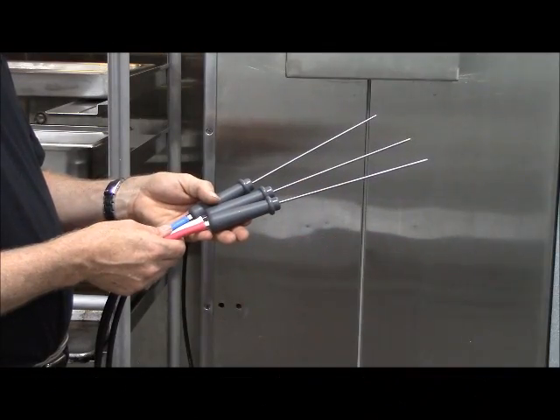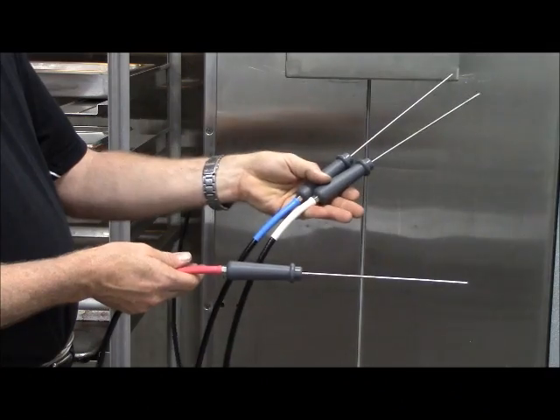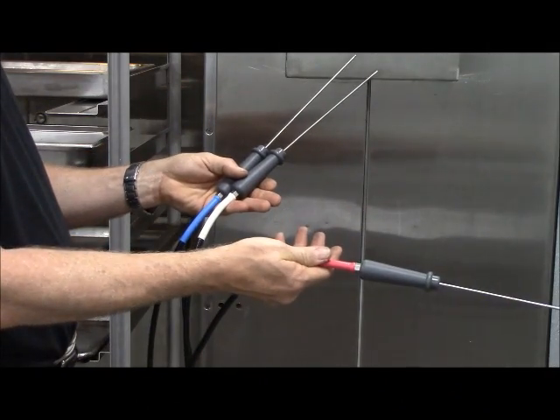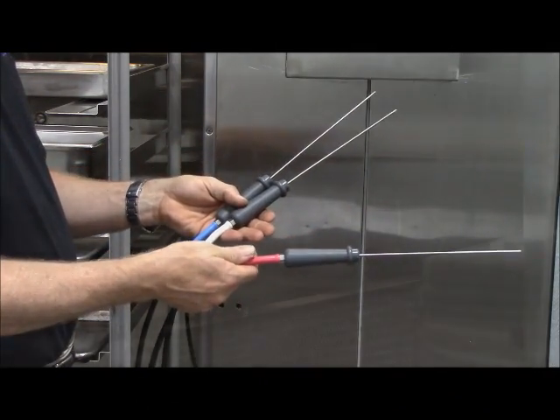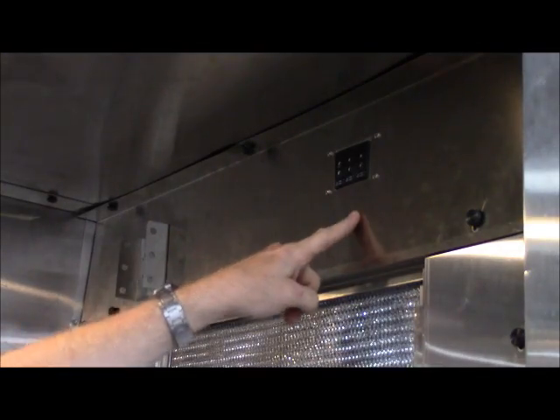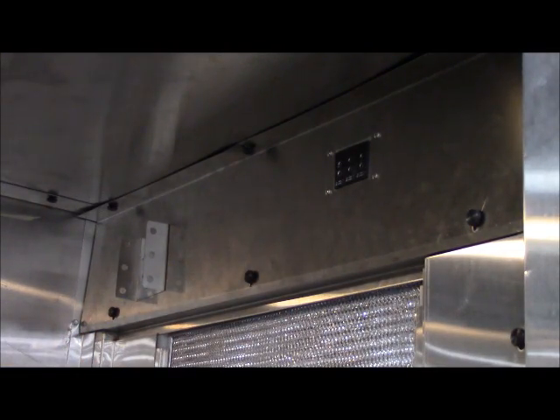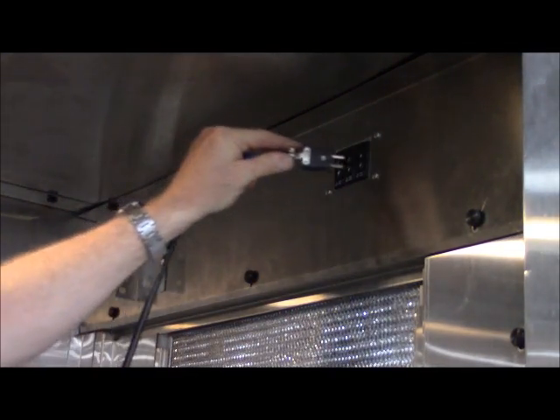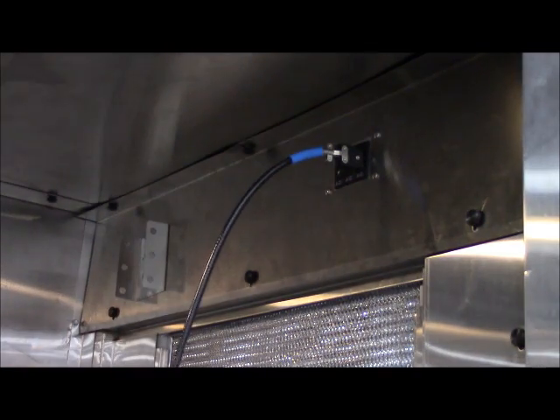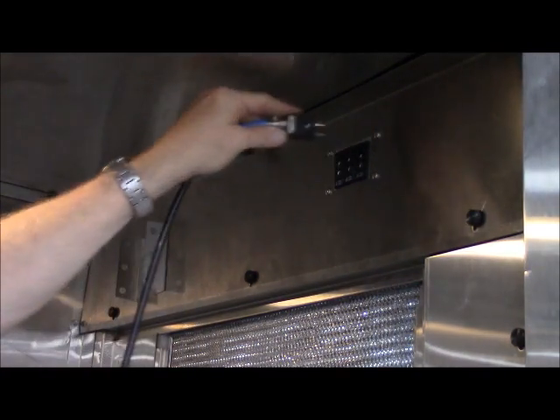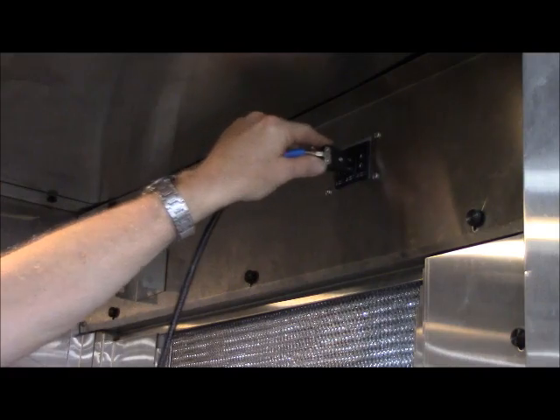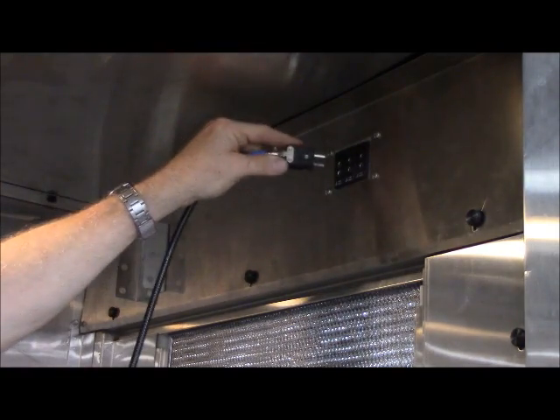To make this happen, the system monitors 2 temperatures, air and food. Of the 3 food probes, 2 are auxiliary probes and 1 is a product probe. These probes are plugged into receptacles along the upper side of the coil. The receptacle for the product probe is the closest receptacle to the door. The probe plugged into the front receptacle becomes the product probe. Any of the 3 food probes will work in any receptacle.